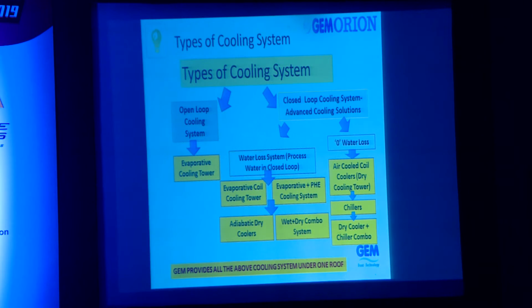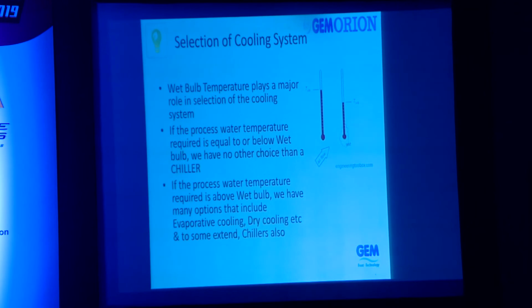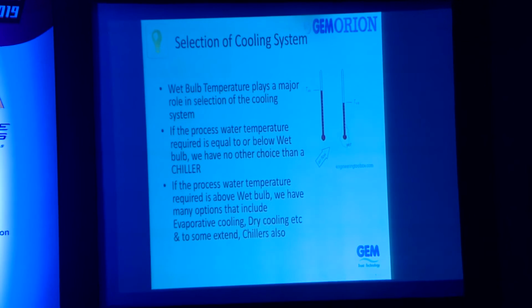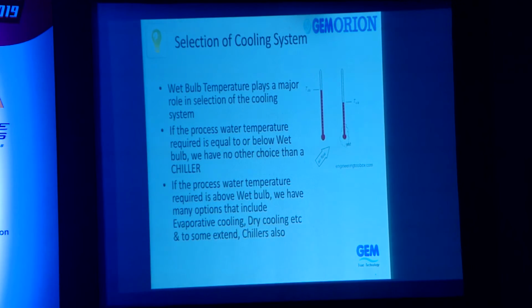And we can also have a wet and dry combination, which is internationally used and called a hybrid system. When there is a situation where we don't have water at all, or the water quality is so bad, or treatment costs are very high, then we talk of zero water loss systems, where we have to use complete dry coolers or chillers, or a combination of dry cooler and chiller. So this is the concept of the advanced cooling systems which can be adopted for our molding and other different applications. How to select the right product is based on the wet bulb temperature, which plays a major role in selection of the cooling system.